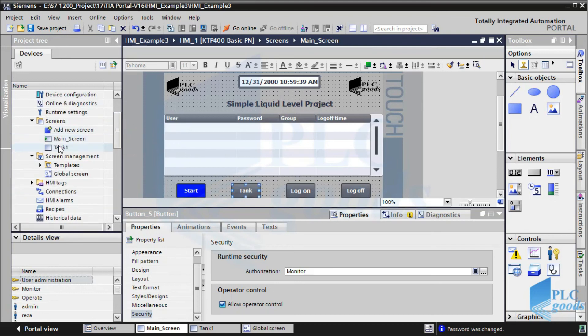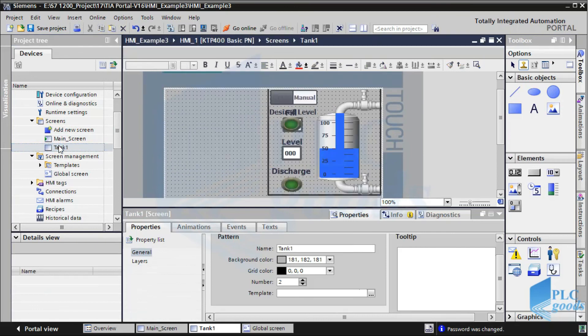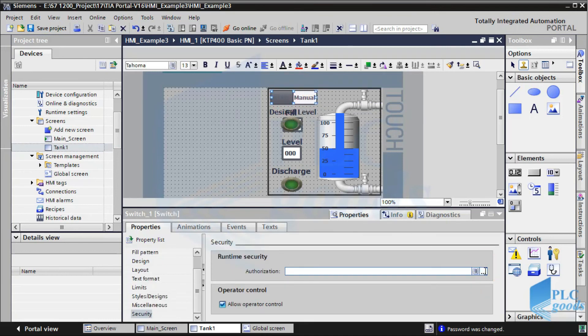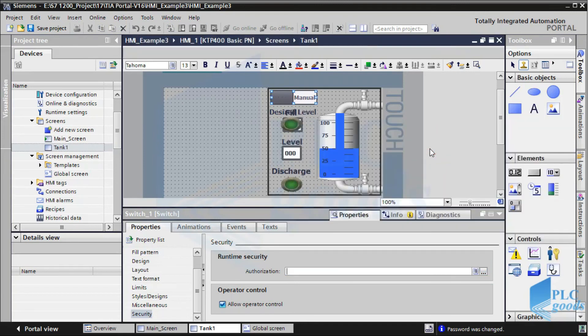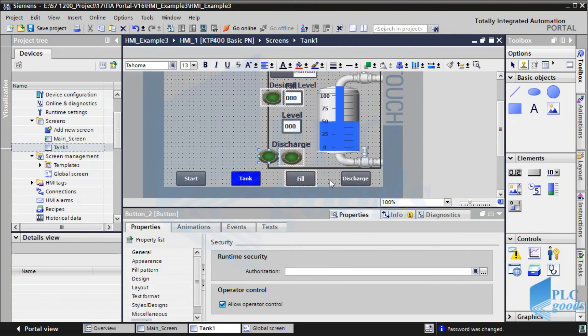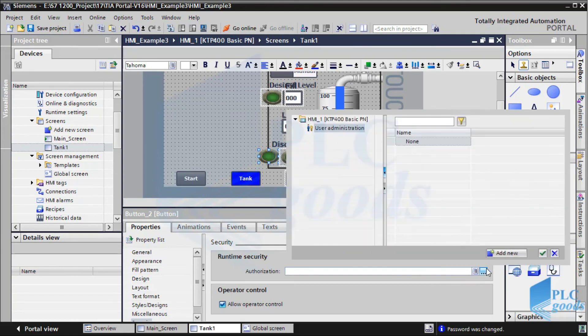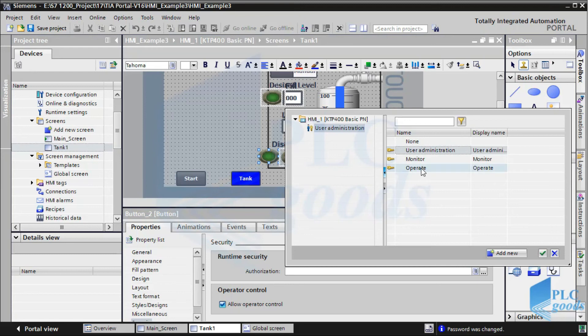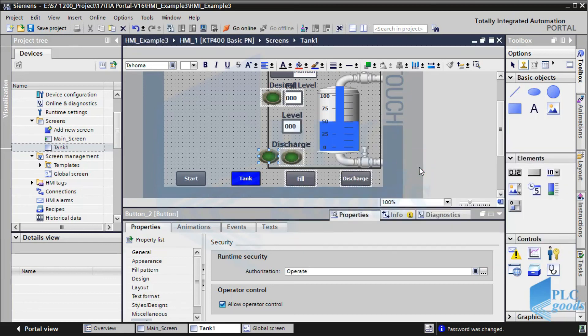If you remember, all three defined groups have monitor authorization, so the four defined users can work with this button and go to the tank screen, but others cannot. Suppose just the admin user can switch between auto and manual control — so in its security part I select user administration, since only the admin group has this authorization. Now suppose the admin and operators group are allowed to work with certain elements, so I select operate authorization in their security parts, because just these two groups have this authorization.